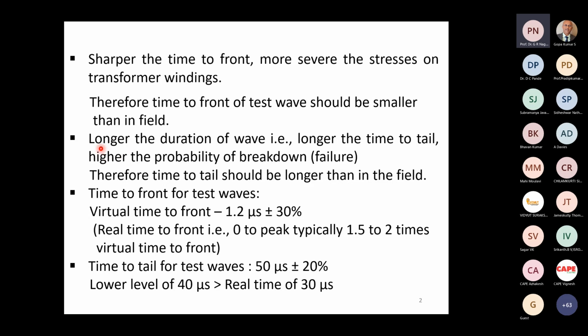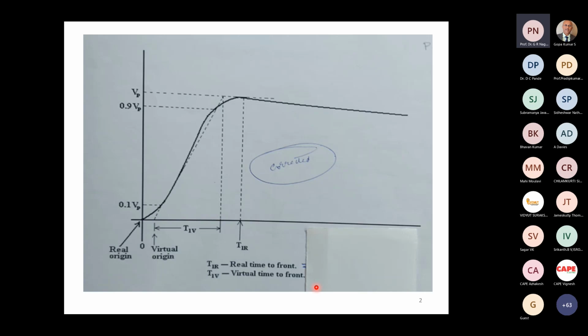On the other hand, if the voltage exists for a longer duration, the probability of failure is higher. That means the longer time to tail is more severe on the transformer to be tested. Therefore, you will find that it's about 30 microseconds to 35 microseconds in real life. The standardized time to tail is 50 microseconds plus minus 20 percent. So even the minimum 40 is higher than the 30 microseconds in real life and can go up to 60 microseconds. These are much longer than the real time of 30 microseconds or even shorter. So now this is how the wave shape is seen. It goes from 0 to the peak in 1.2 microseconds, then reduces to half the value in about 50 microseconds.